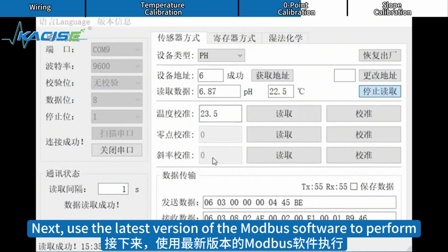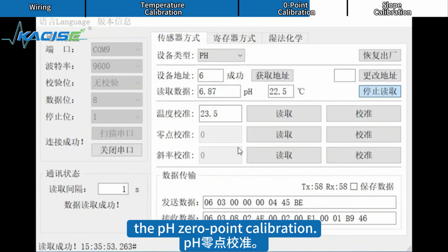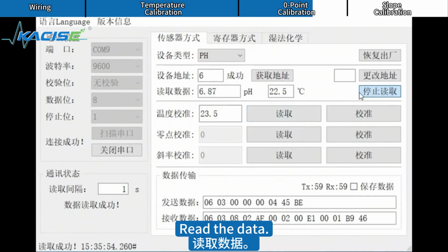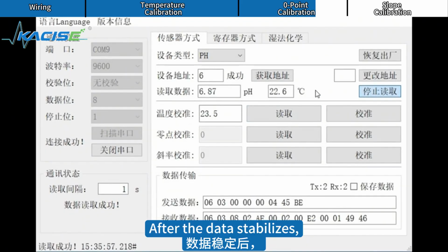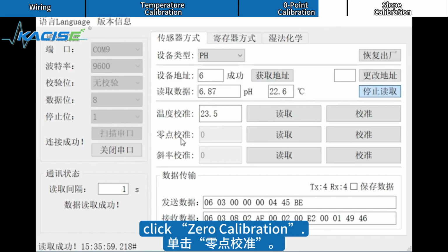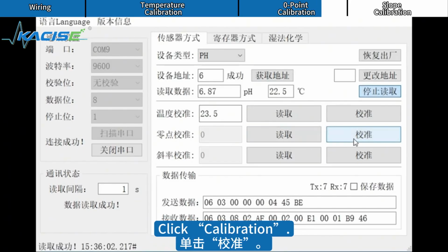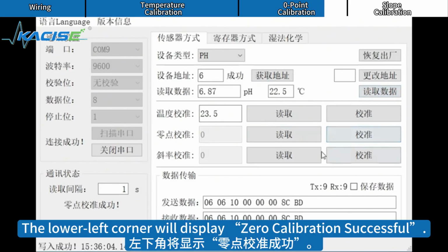Next, use the latest version of the Modbus software to perform the pH 0-point calibration. Read the data. After the data stabilizes, click Zero Calibration. Click Calibration. The lower left corner will display Zero Calibration Successful.